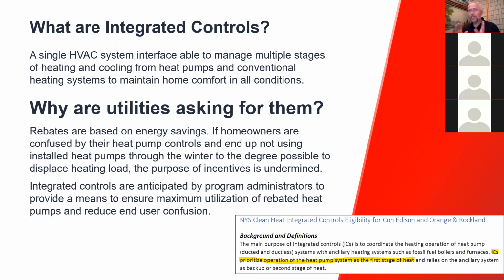I think, at least the way that I think about it, a lot of times what happens with consumers is if they have separate controls, particularly if you've got a remote for the wall mount unit, for instance, on a ductless unit, they may use the ductless unit for a while, and then it gets cold, and either they've heard from friends, neighbors, or one of the installers that they should turn it off at a cold temperature. They'll shut it off, and they'll use their conventional heating system for the rest of the year, or they get one super cold day in December or something like that, and they say, oh, well, that's it for the heat pump, I'm going to use my conventional heating system, and they don't get the benefits.